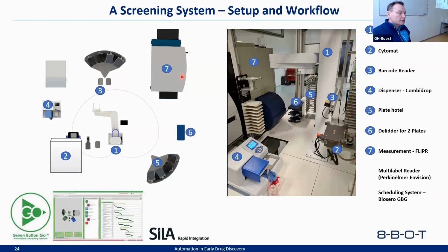This is the measurement device, the FLIPR, quite a complicated device. You can have different plates inside, liquid handling, cell tanks even inside. And as I said before, you have a complete robot inside, and you have an amplifier for the read light, and you can measure a complete 1536-well plate at the same point in time for every well in sub-second resolution. And here's a multi-label reader. It's a PerkinElmer EnVision based on filters.